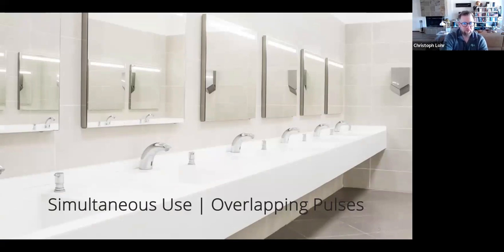Because up until that time, the way to size piping systems was to assume that every plumbing fixture was on simultaneously. So, as an example, if we had a bank of lavatories or a bank of water closets, of toilets, and they were flush valve, those flush valve toilets will have a flow rate of about, you could say, 25 gallons per minute. Now lavatories are much lower than that, but even back then, flush valve water closets were about 25 gallons per minute. Now, if you had 10 of them, that's 10 times 25 gallons per minute, which equals 250 gallons per minute, which would equate to a 4-inch water main to serve those 10 water closets.